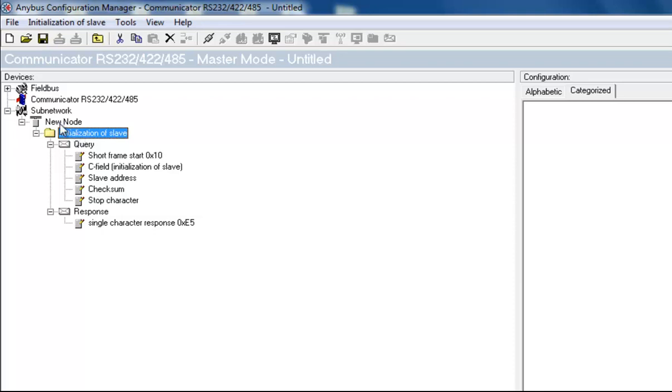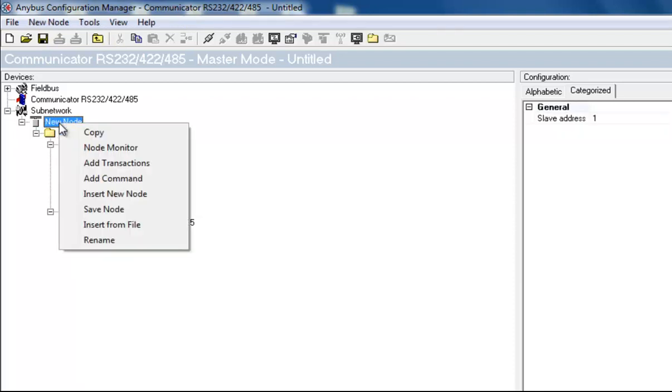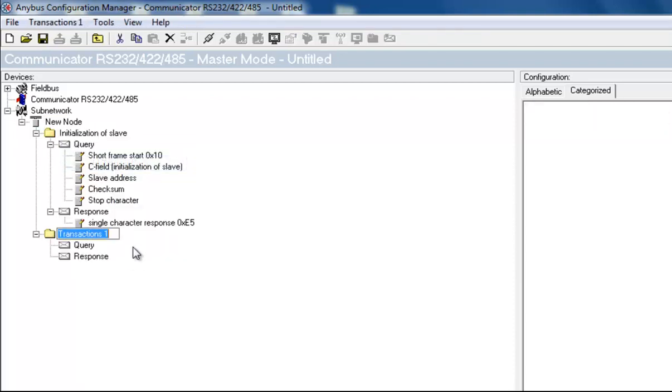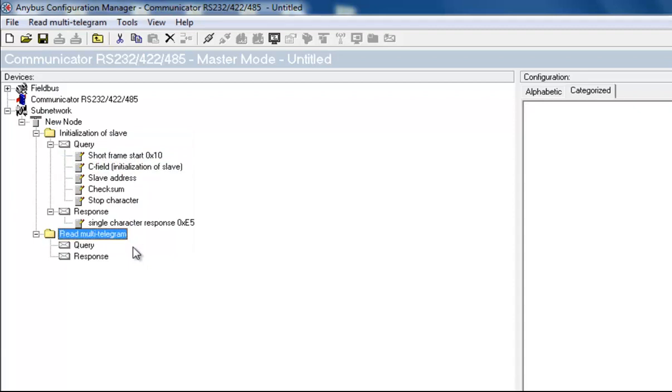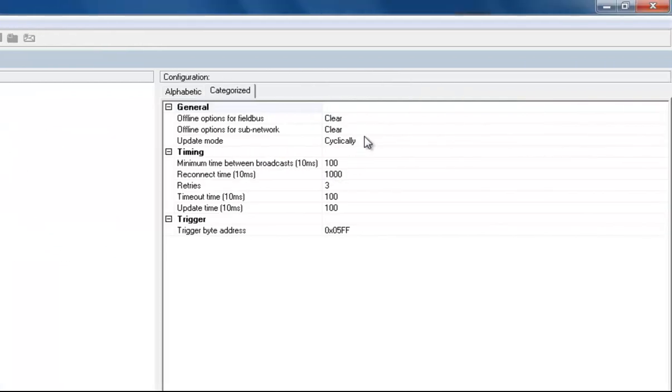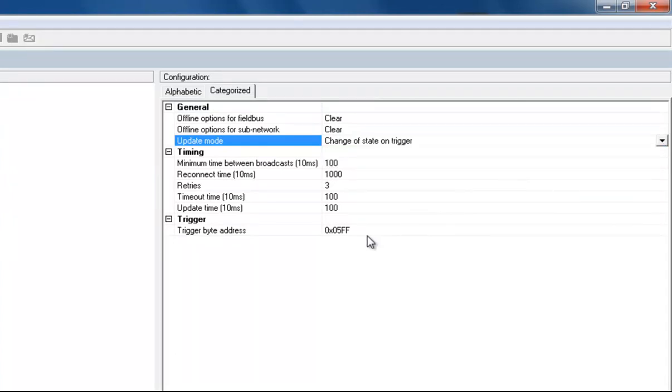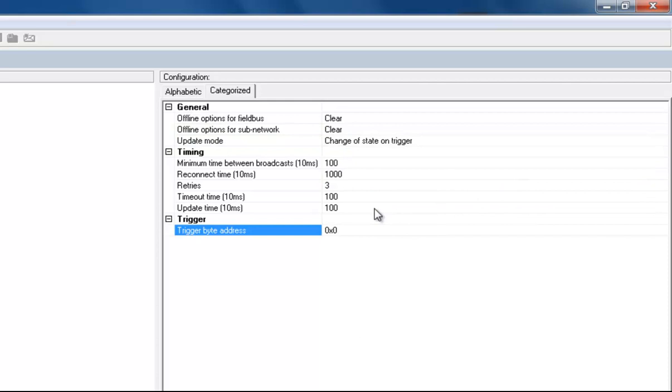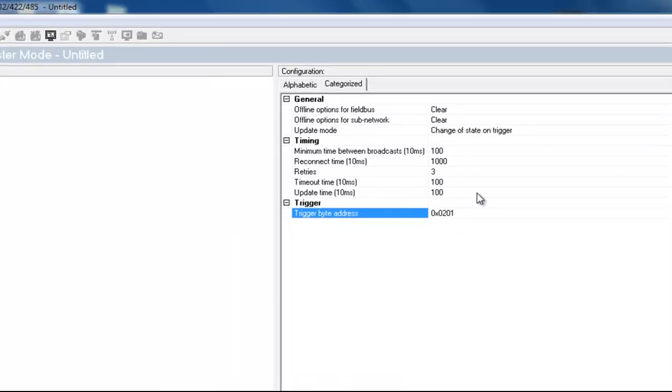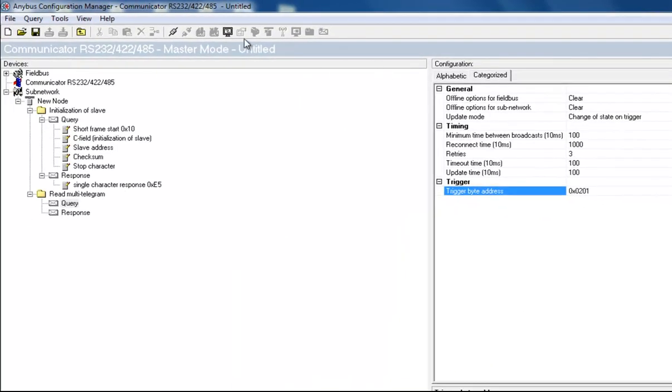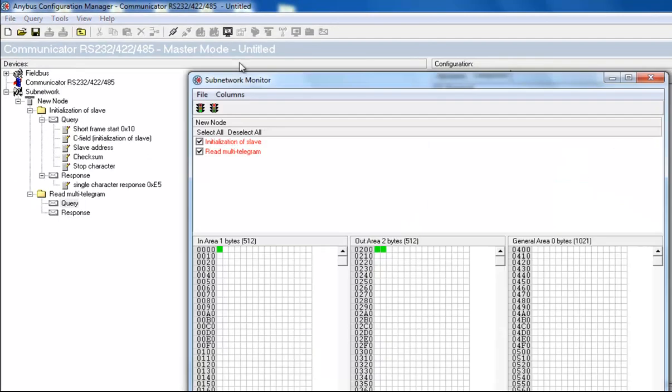I create a transaction and name this readMultiTelegram. I change the update mode to change of state on trigger, just as I did in the query to initialize the slave. I also change the trigger byte address to 201. By looking at the subnetwork monitor, I can see that we now have a second trigger byte on address 201.